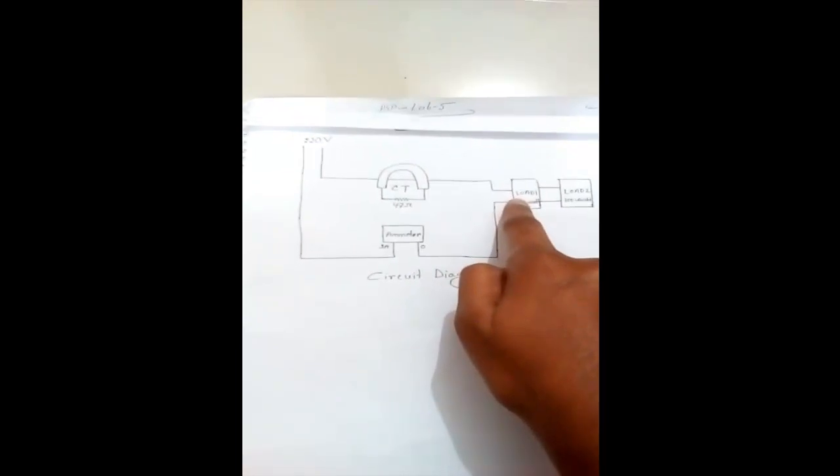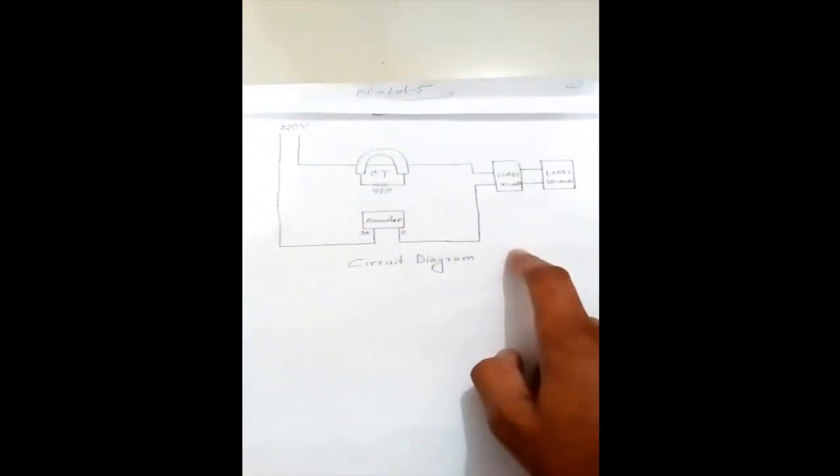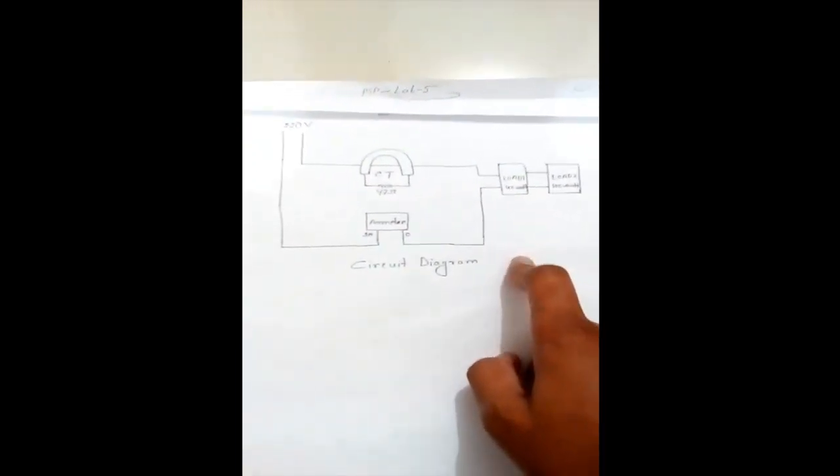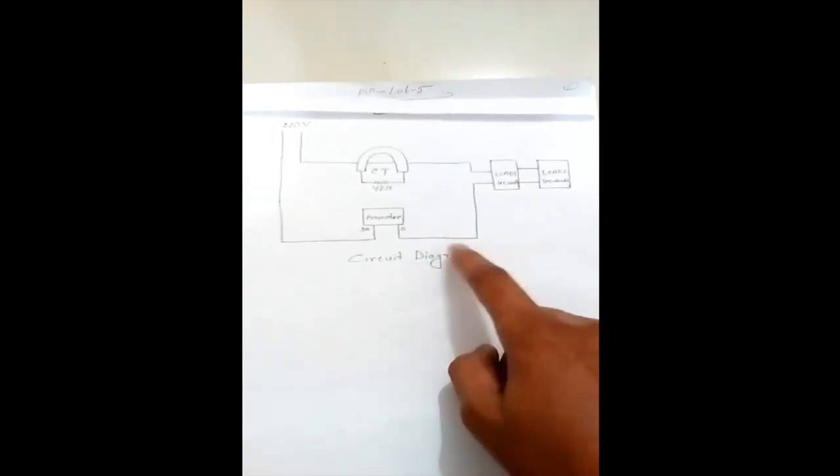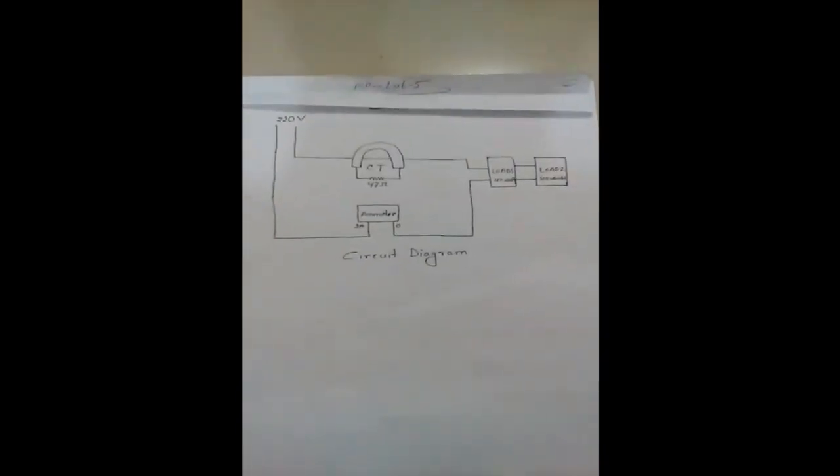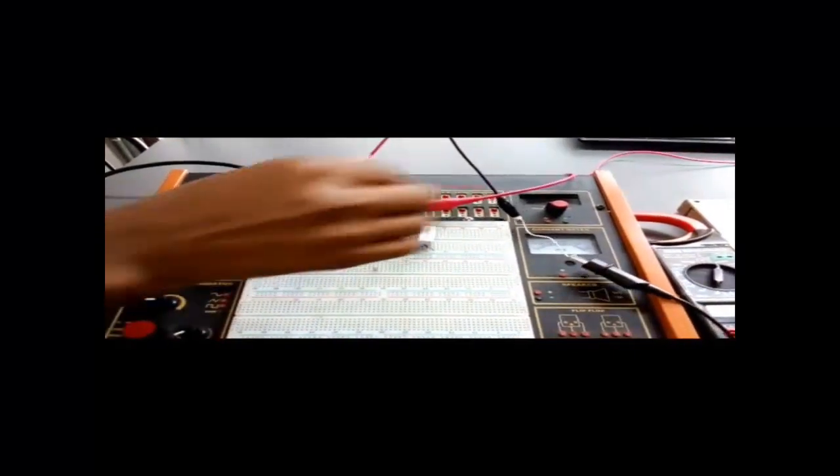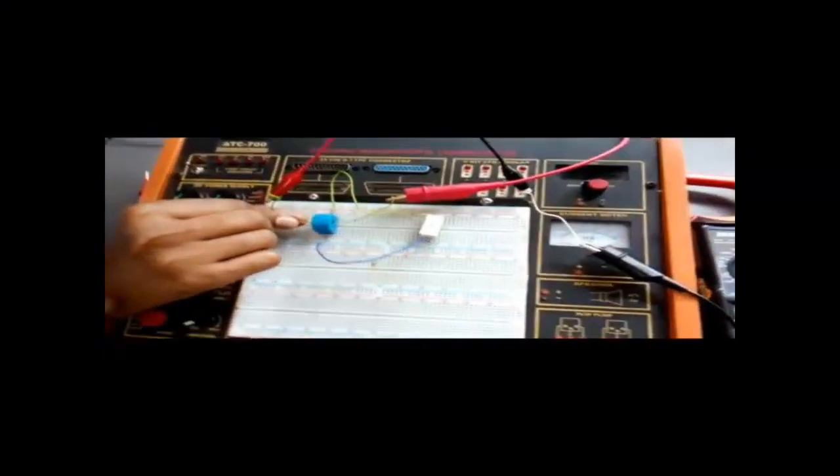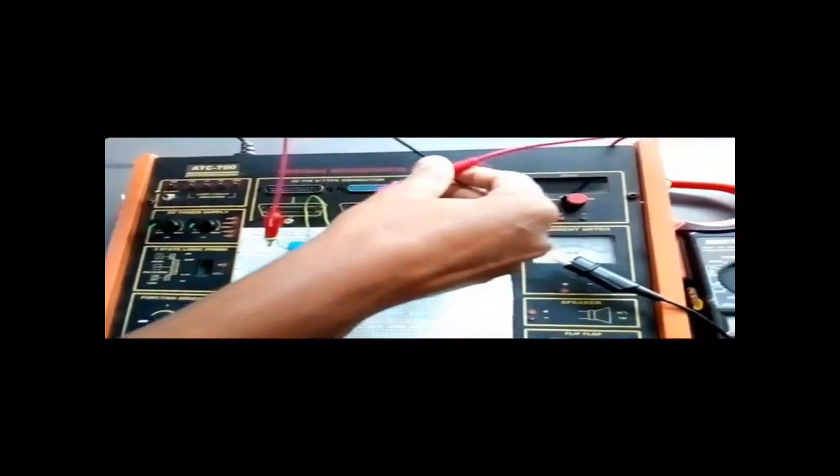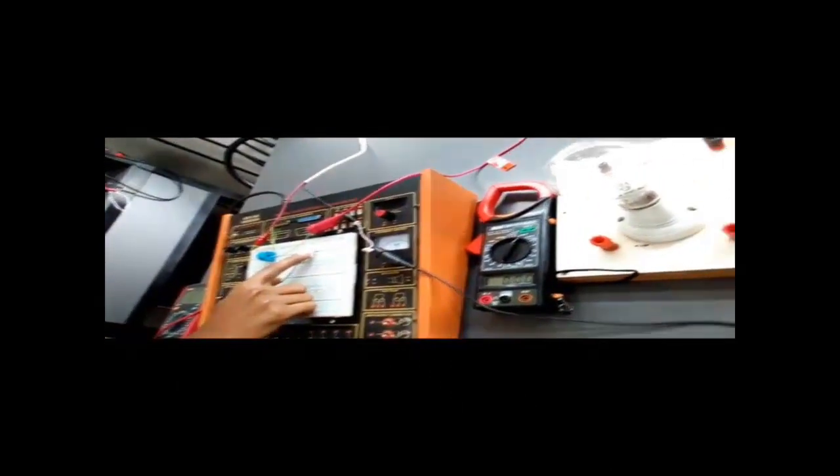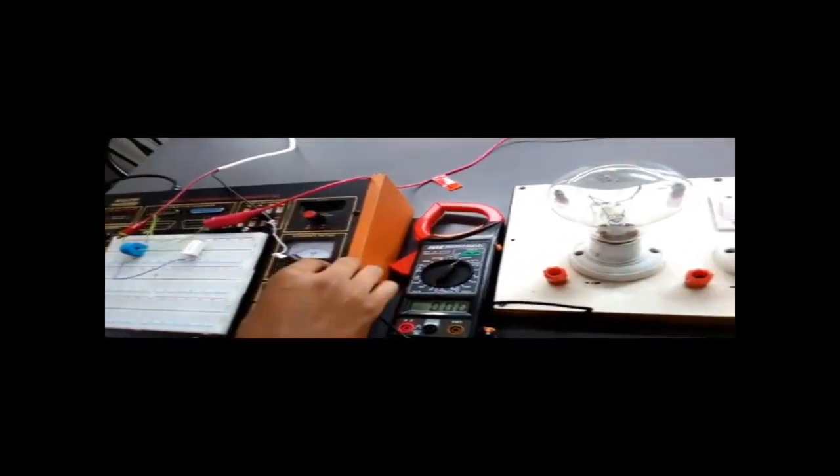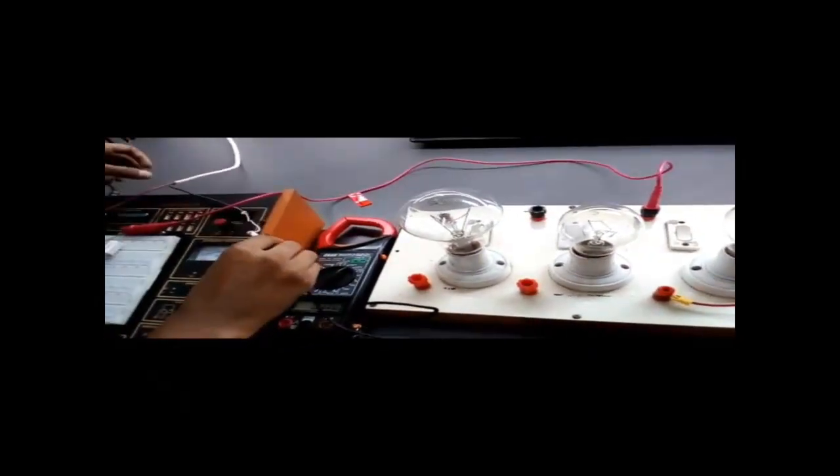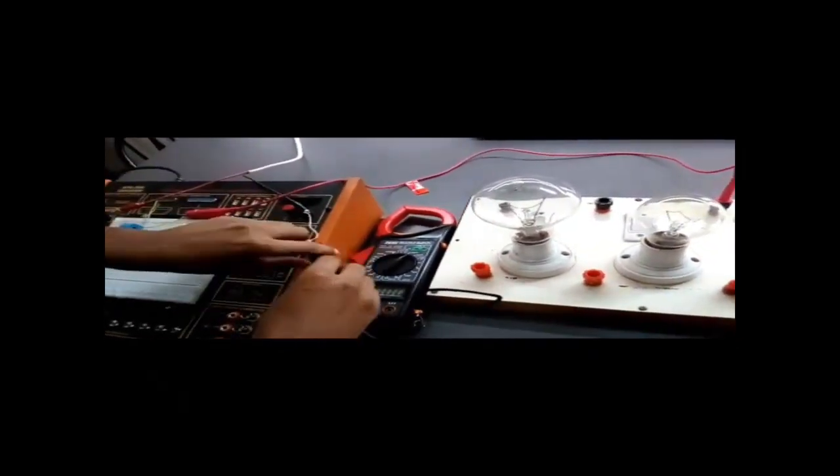Now I'll show you in practice how I set up this connection. This is the 220 volt line - the red wire is the phase which goes through the CT and is directly connected to the load. This is the burden resistor which is directly connected to the CT's secondary side, and the 220 volt neutral line is directly connected to the ammeter.